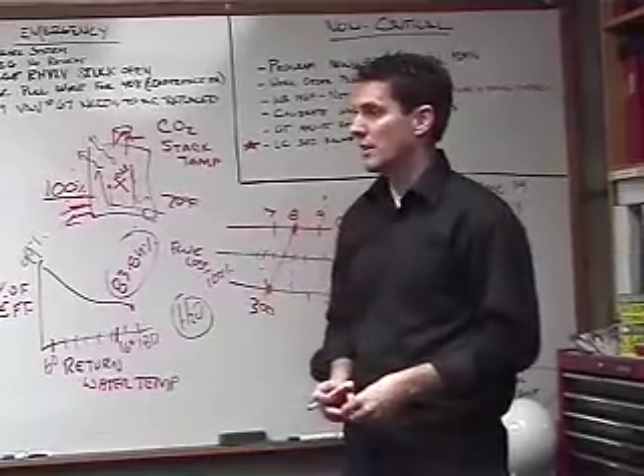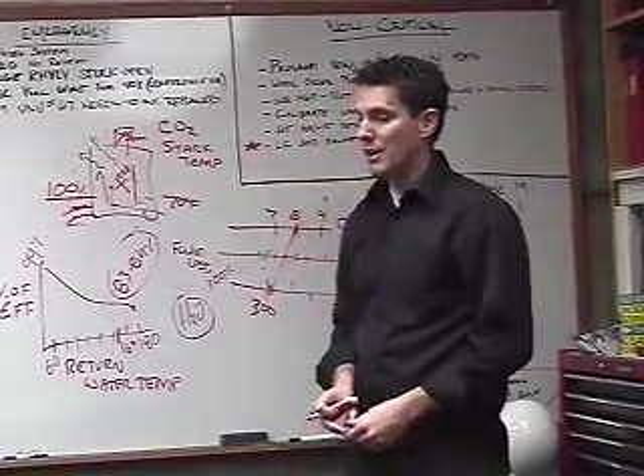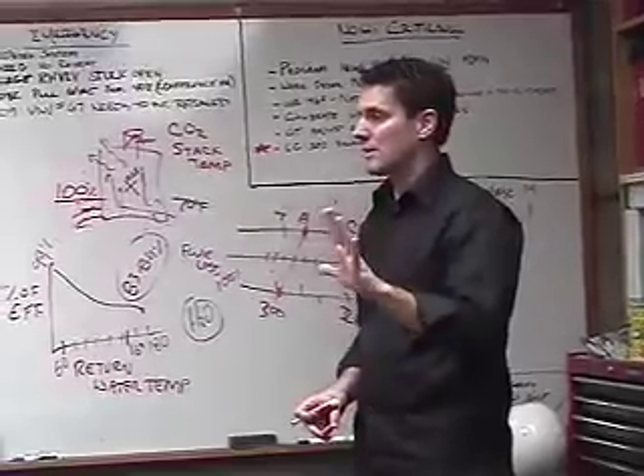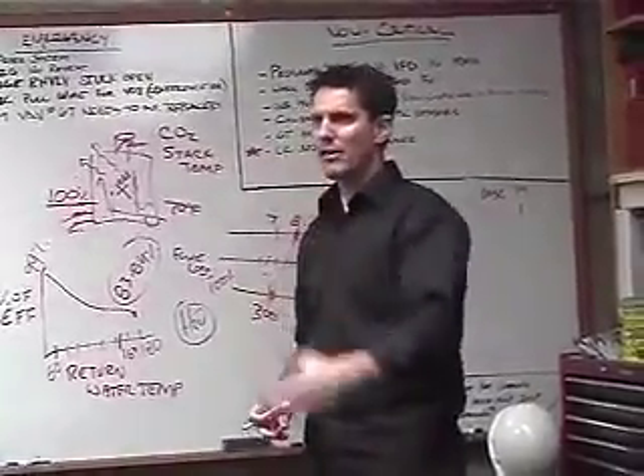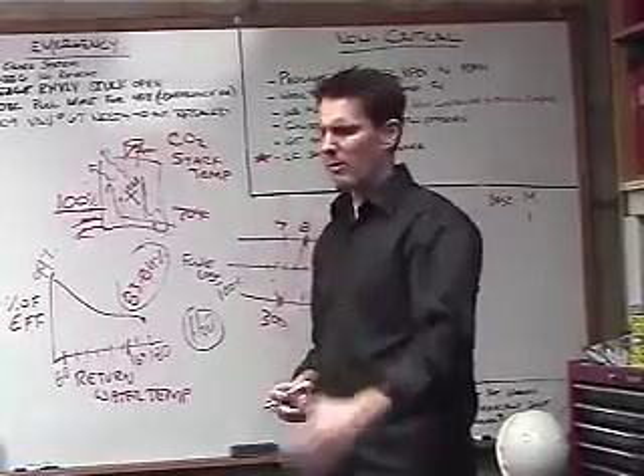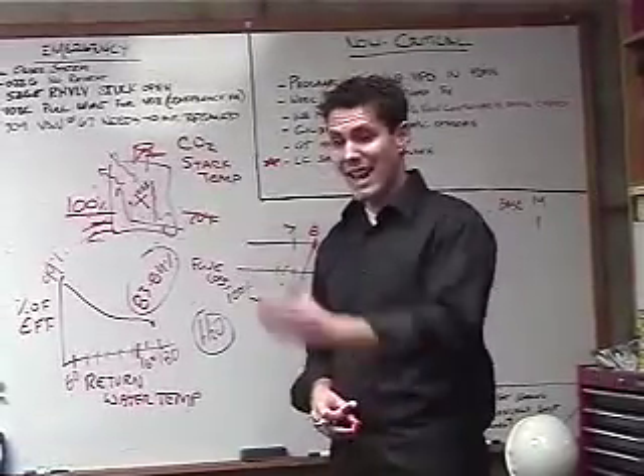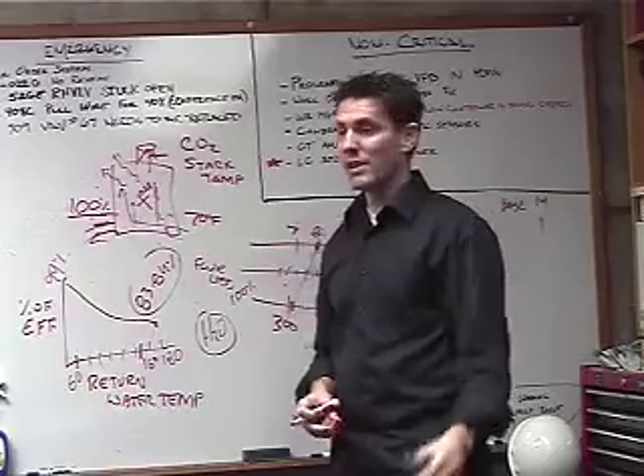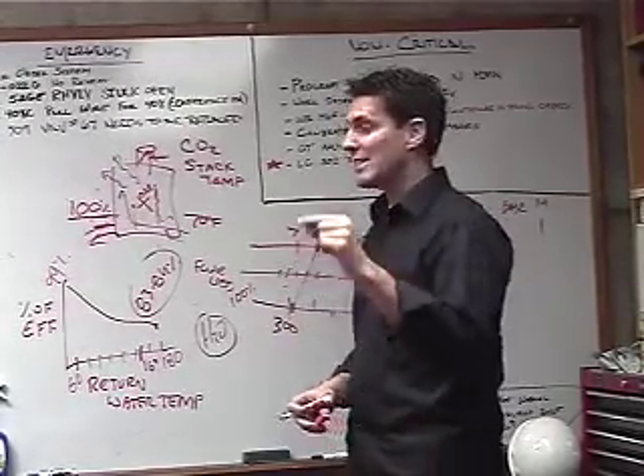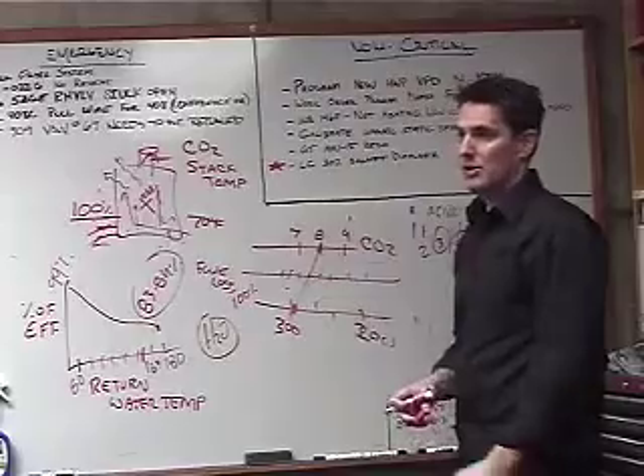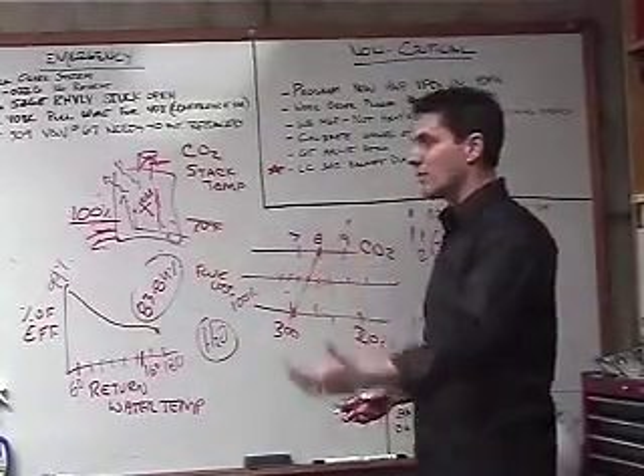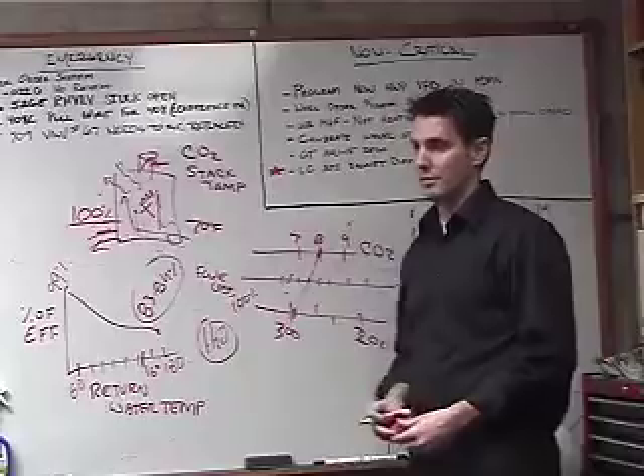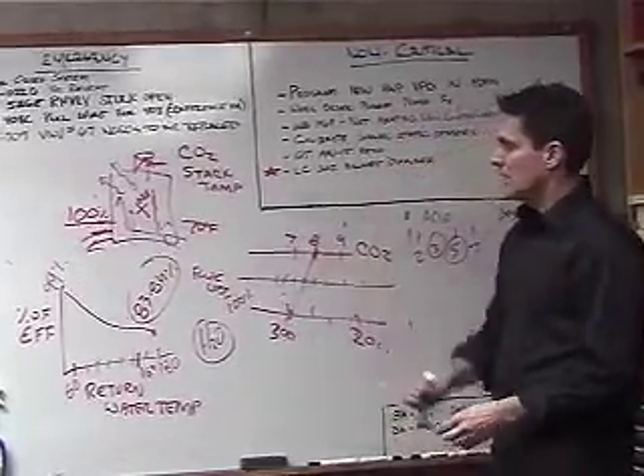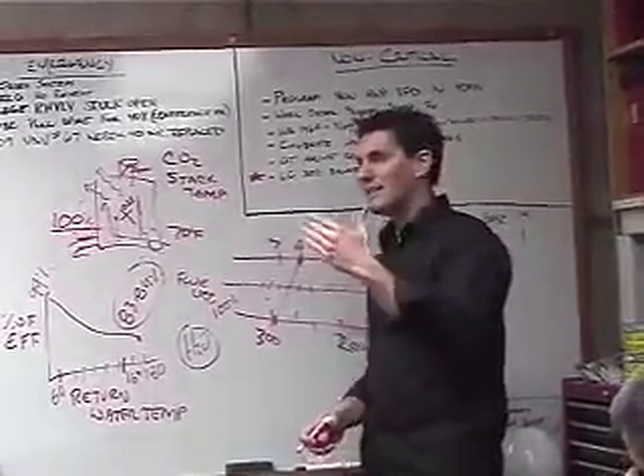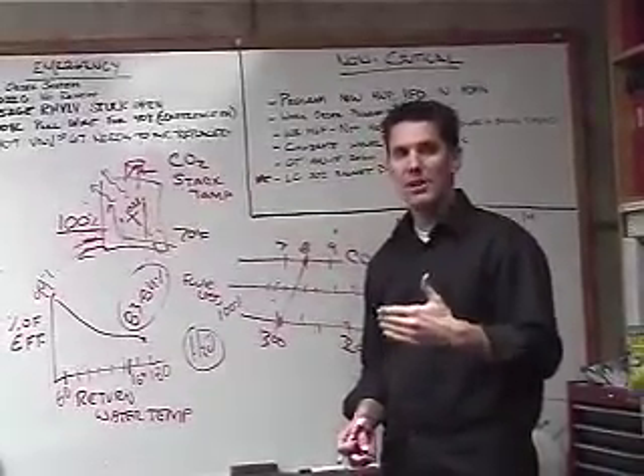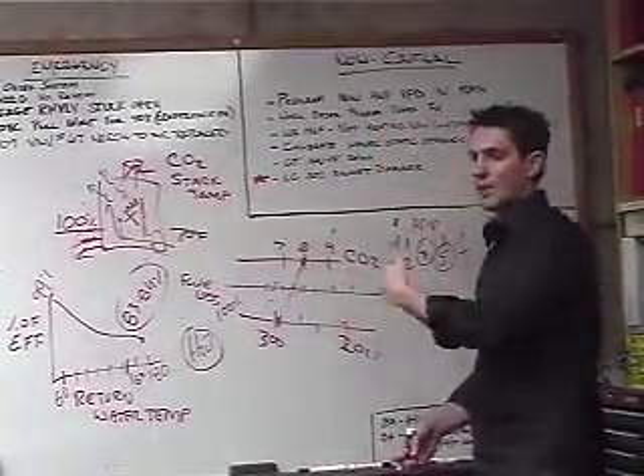And that's our end goal, right? We just did a job up in Boise where they were replacing the boilers after 5 years. And the guys were like, yeah, these boilers have been around forever. They're a good old boiler. Well, how long have they been? About 5 years. Okay, wow, you've got 8 2 million BTU boilers sitting here and replacing all 8 of them after 5 years because they didn't have the permission to condense. So we're putting condensing boilers in there, and these boilers will give them 20, 30 years. And they're thrilled. Okay, so that's the difference between a condensing boiler and a non-condensing boiler, because a condensing boiler gives you the permission to condense because the metal will resist the corrosion.